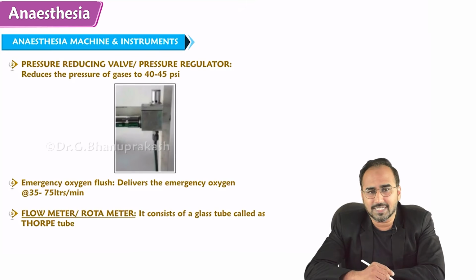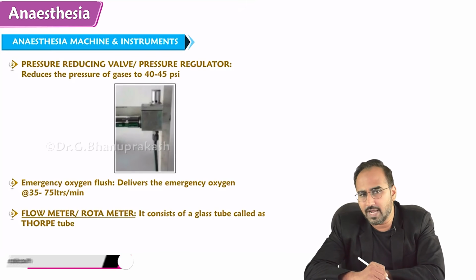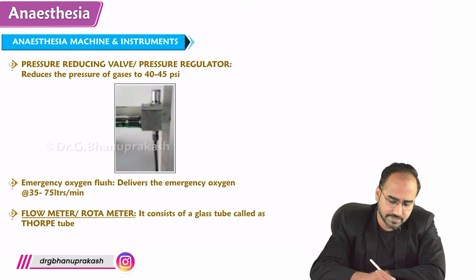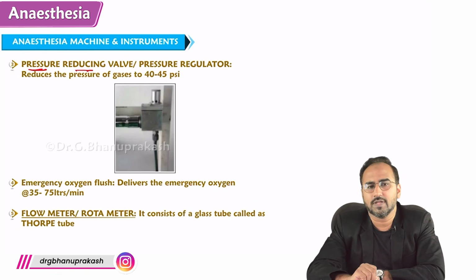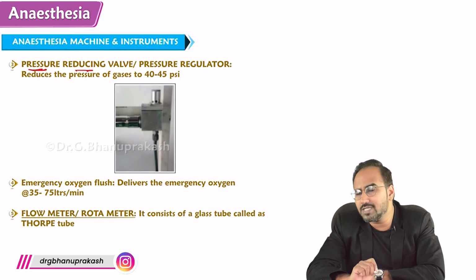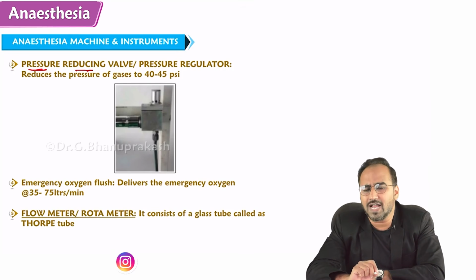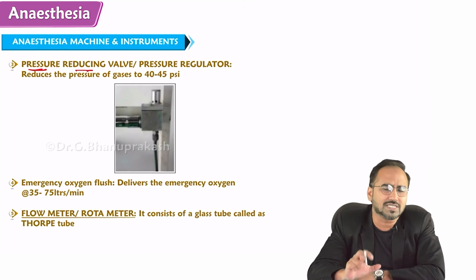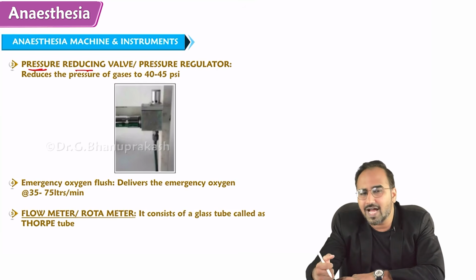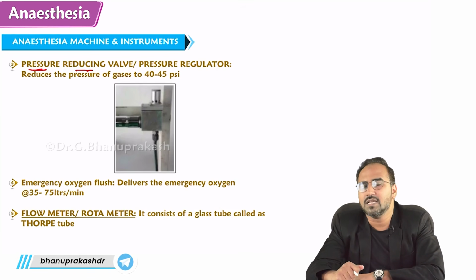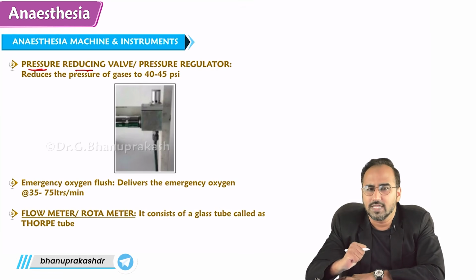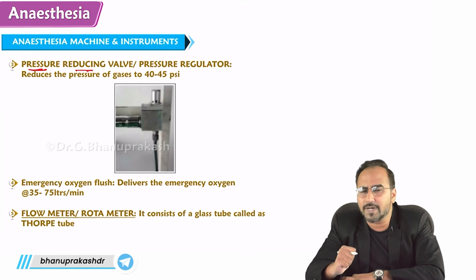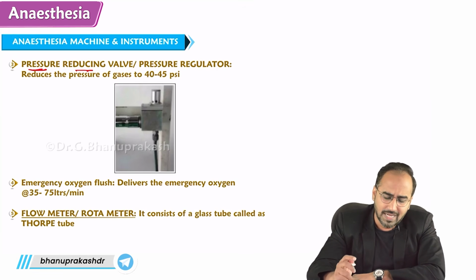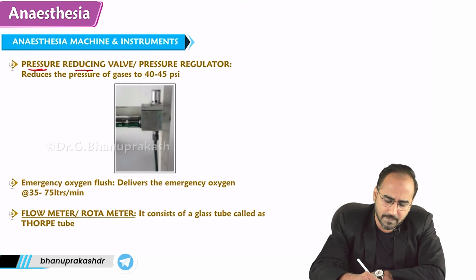Next after pin index system is what? Pressure reducing valve or pressure regulating valve. Now, did I ever teach you about this valve? Because this valve is not seen on the outer surface of the machine. This valve is present on the inner surface. What is the function of this valve? This pressure regulating valve or pressure reducing valve of the machine helps to reduce the pressure.